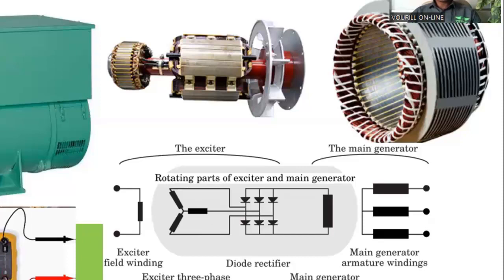That is the same way you test your electric motor windings, your generator armature winding, and even the main field winding. You test for continuity, you test for short to ground, and then, if possible, you test the value of the resistance to see if it is still as it was when the machine was working properly.